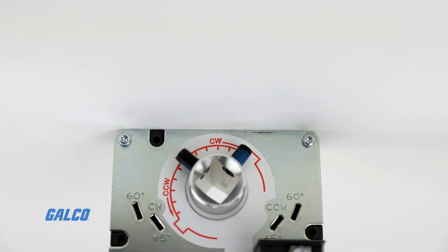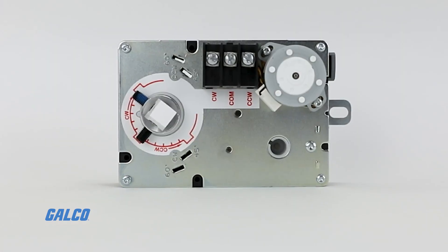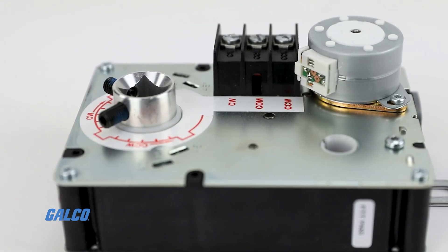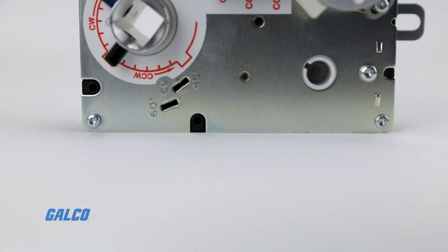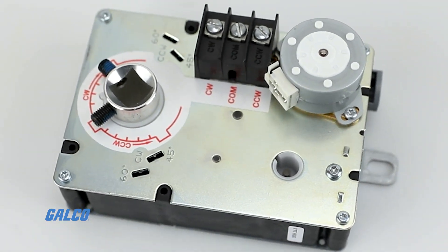These damper actuators have a selectable 45, 60, and 90-degree rotational stroke in both clockwise or counterclockwise directions. With a torque rating of 35 inch-pounds and non-spring return fail-safe mode, the ML6161 is made with plenum-rated plastic and steel and has an aluminum hub shaft adapter.